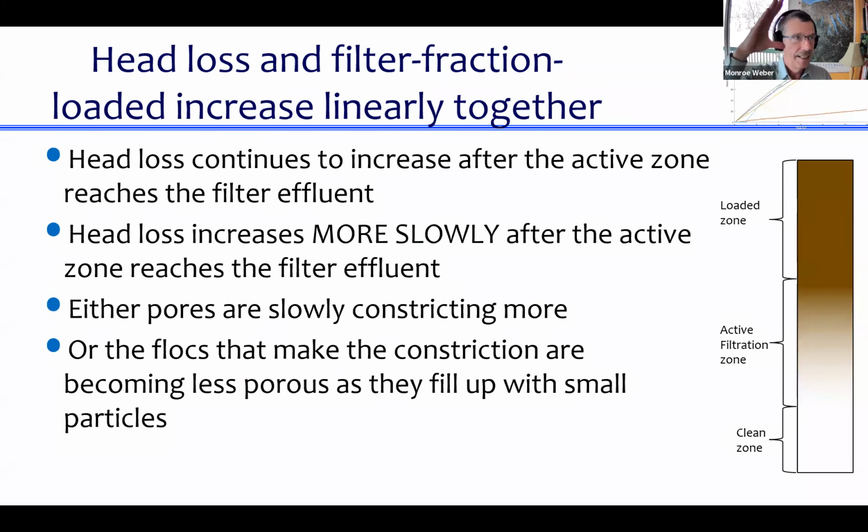So remember, here's the idea. Each pore is slowly loading with particles and gets as small as it can possibly get until the velocity inside that pore is so fast that no more particles can attach. At that point, all the particles that come up to that pore just blow right through and keep on going deeper into the filter. So the number of pores that you have to go through to get to a pore that's open and ready for more particles to be deposited is a function of how much dirt, or flocs, have been deposited in the filter thus far.